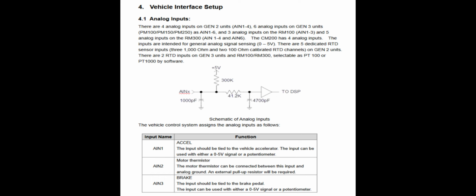This is because the controller actually reads 0 volts as a fault state or a short circuit. So there's a little bit of an offset provided for the analog pins just to account for that possibility of a short or something else going wrong with the analog signal.